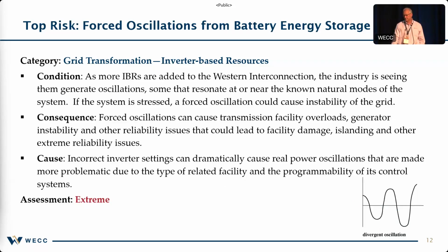Here's a new one you may not have seen: forced oscillations from battery energy storage systems. I don't think there's a standard that ever talks about forced oscillations from battery energy storage systems. The Western Interconnection has had at least 2 or 3 events in the immediate past where we had a forced oscillation occur due to battery energy storage system control systems. So we consider this probably one of our most extreme, highest risks on the interconnection right now.